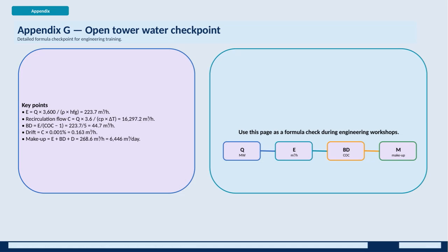Here we have the appendix section focusing on the open tower water checkpoint, which is an essential formula review for engineering training. This training module covers the integration of Badham's coastal data center water supply, including seawater reverse osmosis desalination, direct liquid cooling, and cooling tower systems. Let's highlight the key calculations here. First, E represents the evaporation rate, calculated as Q times 3,600 divided by the product of density and latent heat of vaporization, giving us about 223.7 cubic meters per hour. This value is critical for understanding water loss through evaporation.